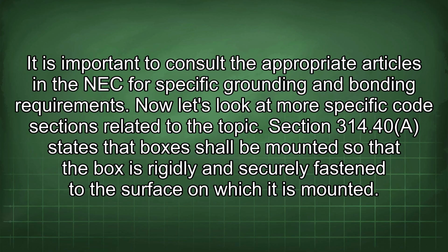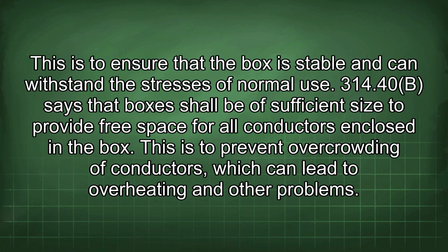Section 314.40 states that boxes shall be mounted so that the box is rigidly and securely fastened to the surface on which it is mounted. This is to ensure that the box is stable and can withstand the stresses of normal use. 314.40(b) says that boxes shall be of sufficient size to provide free space for all conductors enclosed in the box. This is to prevent overcrowding of conductors, which can lead to overheating and other problems.